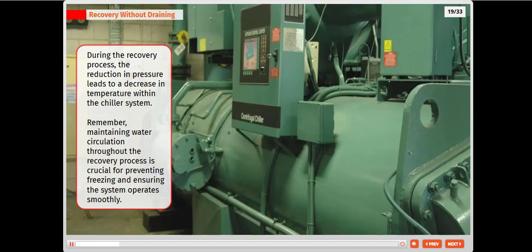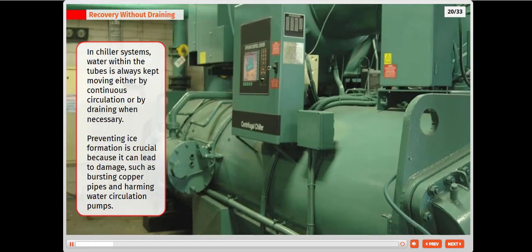During the recovery process, the reduction in pressure leads to a decrease in temperature within the chiller system. Remember, maintaining water circulation throughout the recovery process is crucial for preventing freezing and ensuring the system operates smoothly. In chiller systems, water within the tubes is always kept moving either by continuous circulation or by draining when necessary. Preventing ice formation is crucial because it can lead to damage, such as bursting copper pipes and harming water circulation pumps.